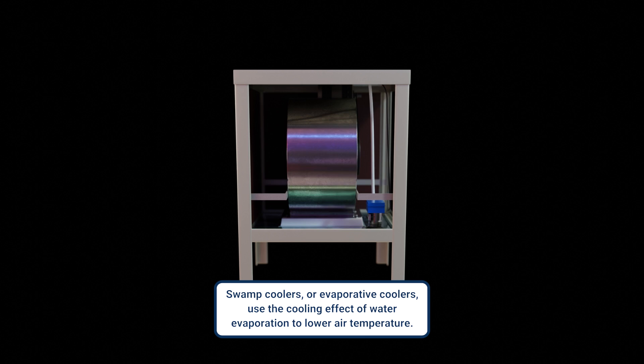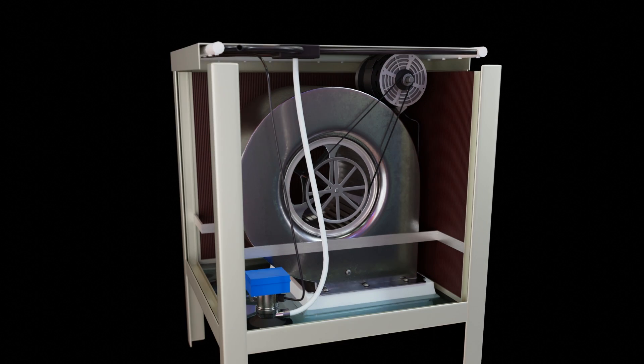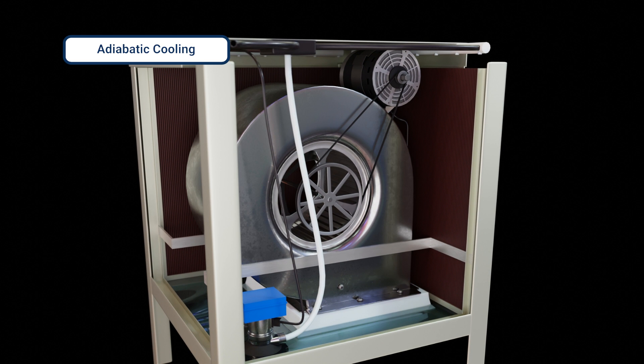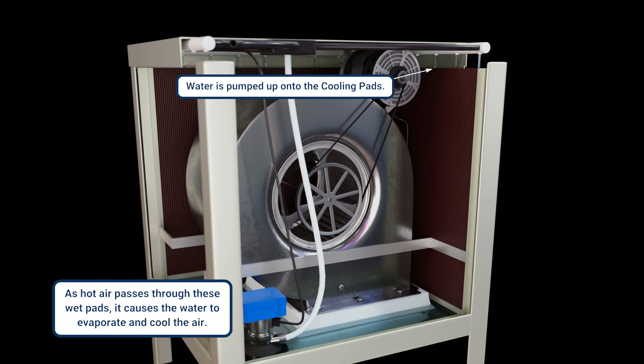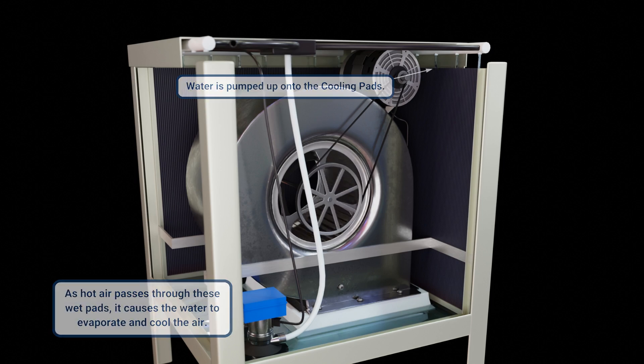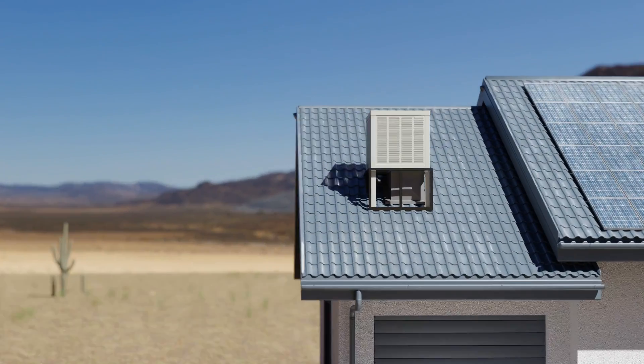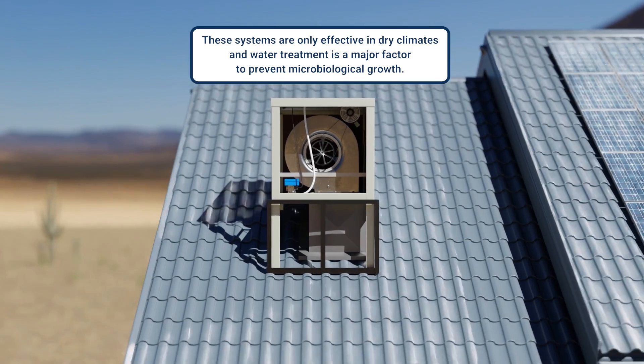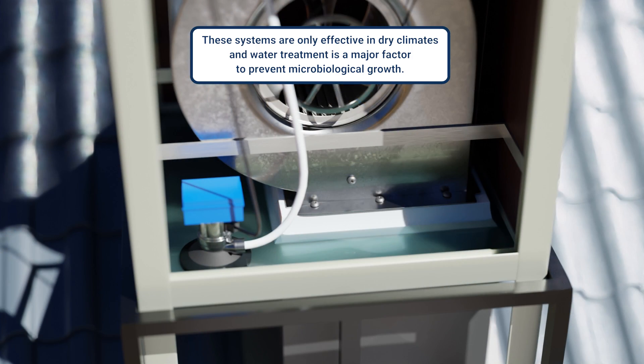Swamp coolers, or evaporative coolers, use the cooling effect of water evaporation to lower air temperature. This is known as adiabatic cooling. These systems are ideal for dry climates. They pass the air over water-saturated pads, cool it via evaporation, and then circulate it through the space. These systems are only effective in dry climates, and water treatment is a major factor to prevent microbiological growth.